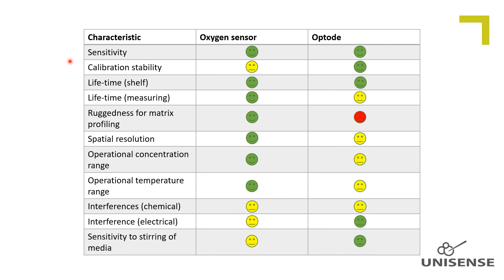Calibration stability. The optode is superior to the amperometric sensor in terms of signal drift. Therefore the optode is recommended for long-term monitoring in incubations, and it is also recommended to use the optode for our microrespiration system.